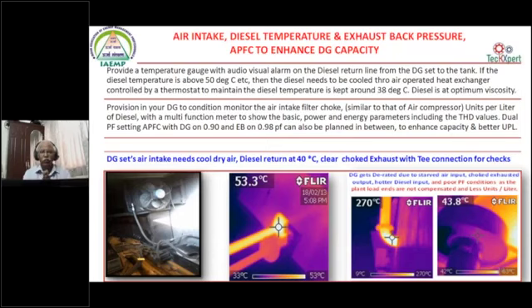You can go for units per liter savings. You can have excellent savings when you are able to fully utilize the loading of the generator in the efficient region between 60 and 80%. A generator operated at 50% will consume only 3 to 3.2 units per liter. A generator operated at around 80% will generate 3.6 units per liter. This is what we can visibly see, and we can definitely improve upon it.